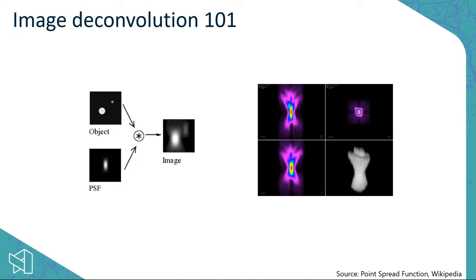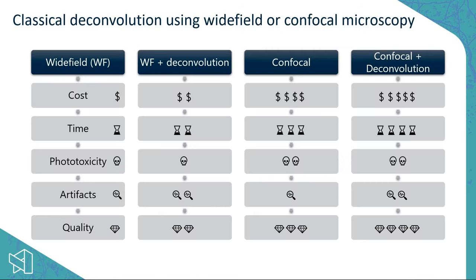If one can know what the point spread function is, and we already have an image, then we try to go back to creating a true image of the object — closer to the ground truth. Deconvolution using a measured or estimated point spread function is what I'm calling classical deconvolution. Here you can see how classical deconvolution can be used in both wide-field and confocal microscopy.